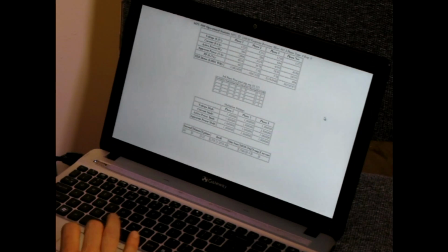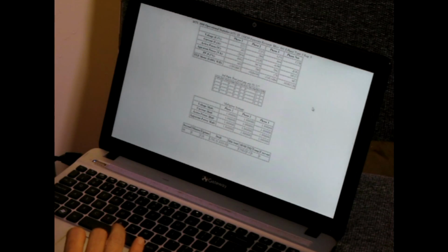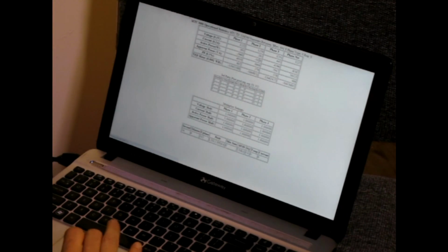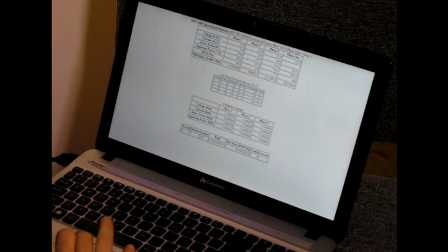So we're looking at the MTU stats page, and what we want to check is the active power on each phase. It's also good to take a look at the voltage as well. You can see that there's a decimal place that's not shown here. So when I show 122.2, that's 122.2 volts per phase. We have the current, which also has a decimal point, and the active power and apparent power.